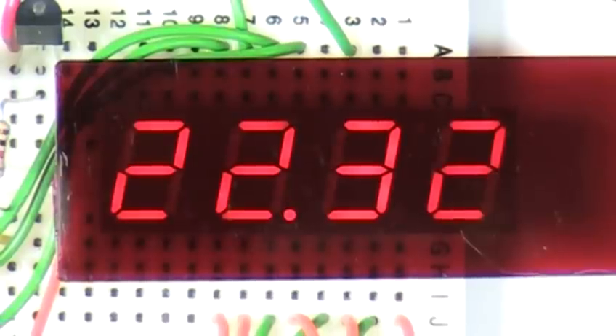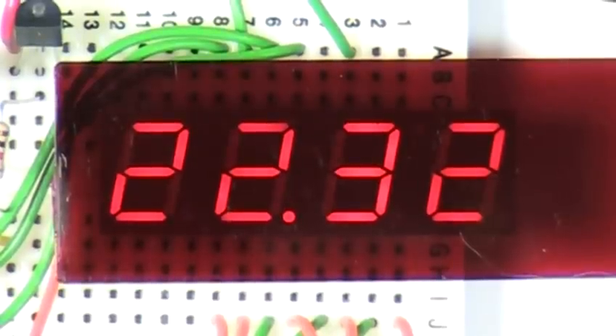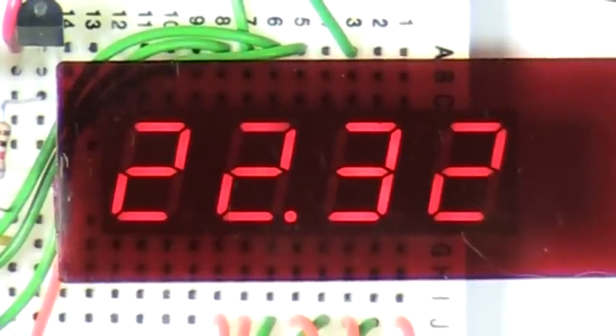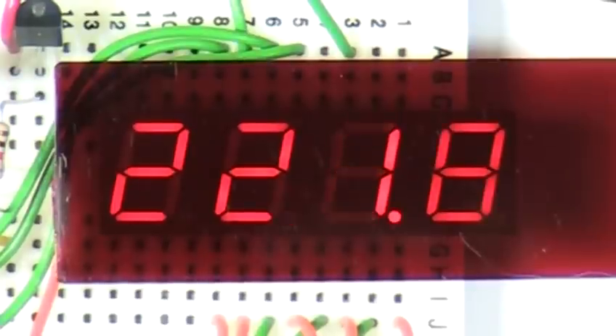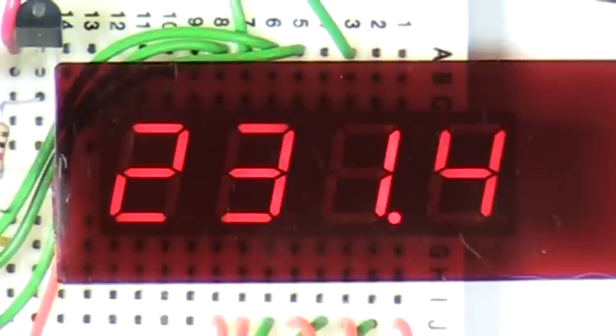Okay, as you can see, the frequency counter is fluctuating between 22 and 23 Hz, with the function generator set to 23.4 Hz. Now, let's increase the input signal to 22.36 kHz, and the frequency counter is reading 22.32 kHz. And with the input signal set to 232.08 kHz, the frequency count reads 231.4. So it's obvious there's some difference here, but how far off are we in percentage?